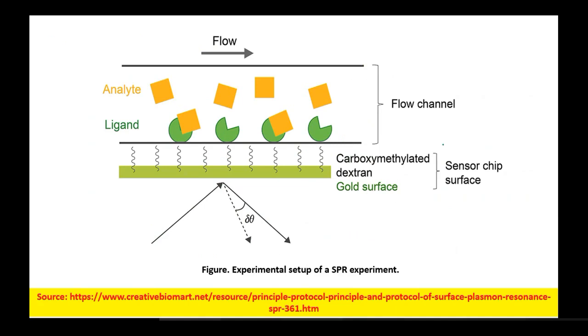Over the gold surface, carboxymethylated dextran or carboxylated dextran can be immobilized, and then the ligand is immobilized over there. We allow the analyte to pass through; if there is affinity for the ligand by these analytes, they will attach onto the ligand surface. After analysis is completed, you can flush the system with washing buffer so these sites will be regenerated.